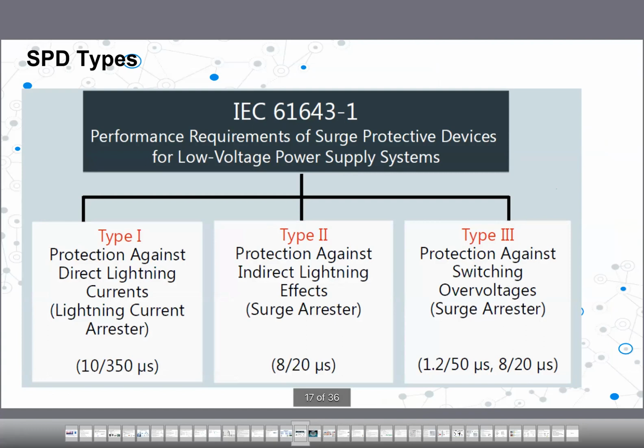Down the line. So type 1, we use to protect against direct lightning, this current wave. Type 2, normally we use to protect against indirect lightning. Type 1 for surge current, type 2 for surge indirect. So this is the waveform that we need to handle. Then type 3, we use for switching type of overvoltages. So try to remember that there are three types: type 1, type 2, type 3.